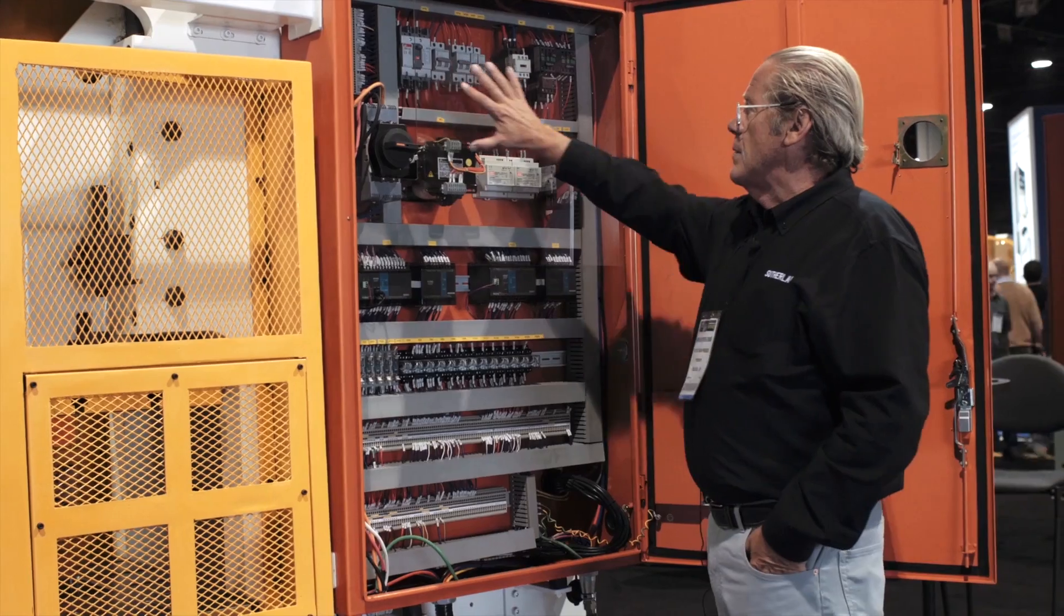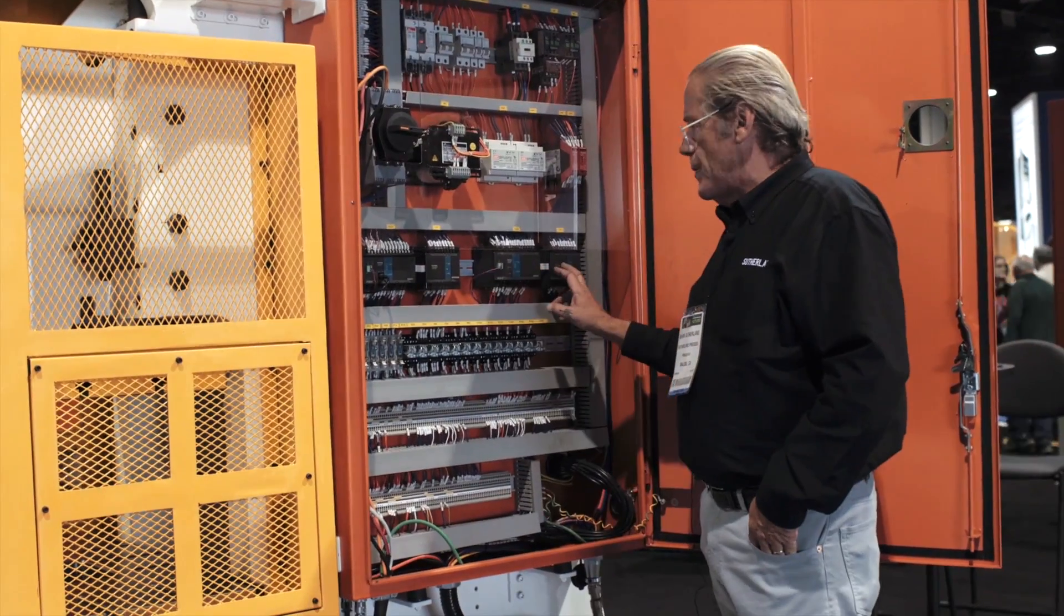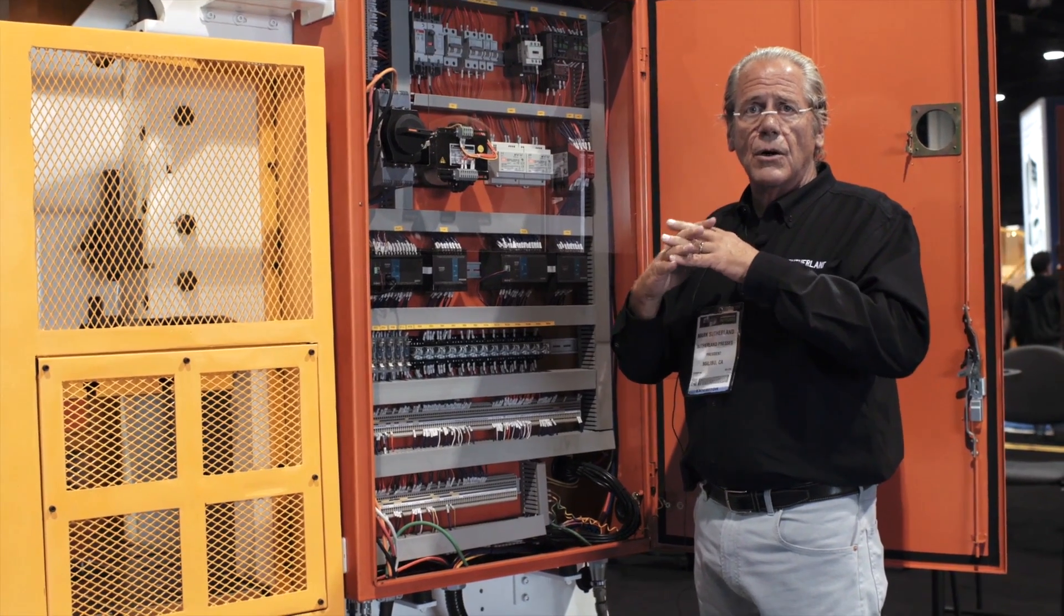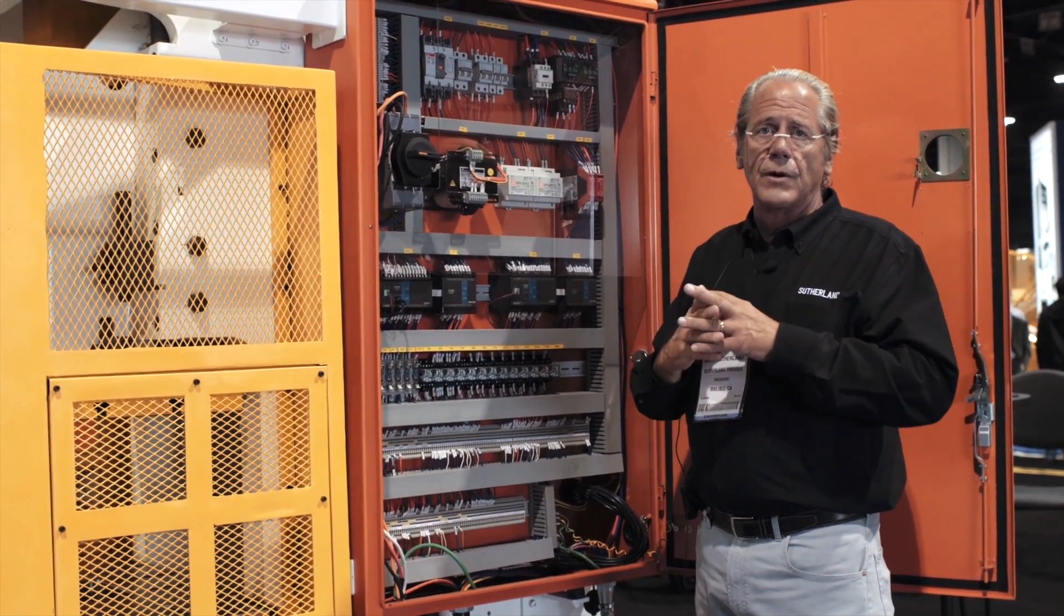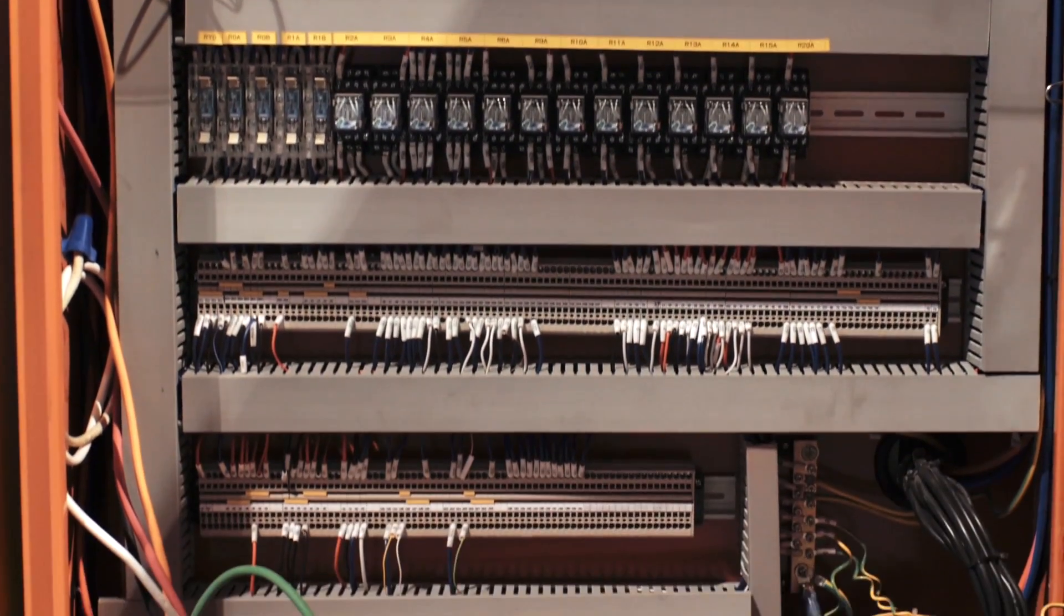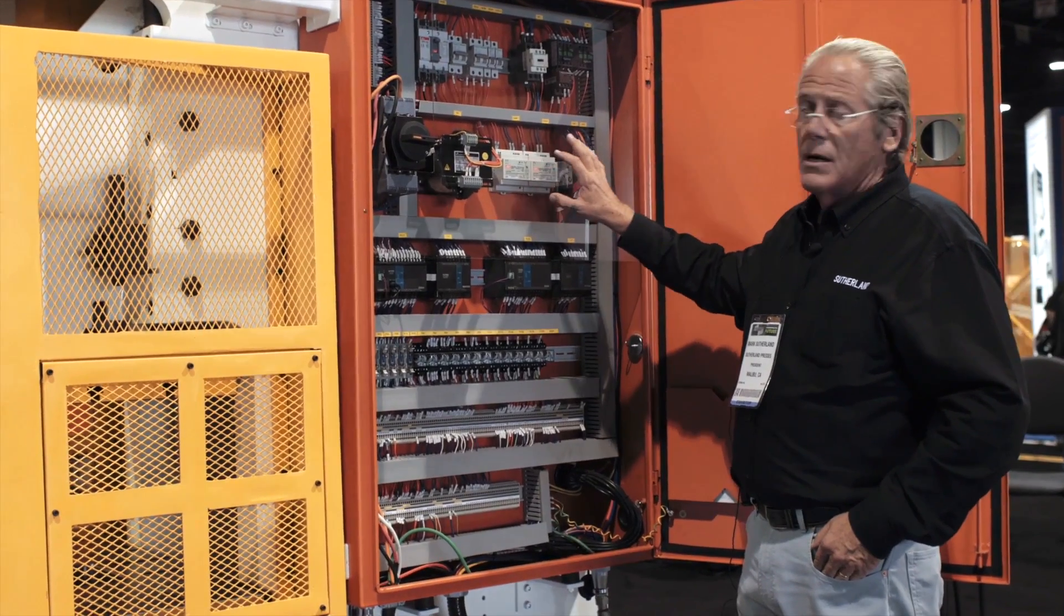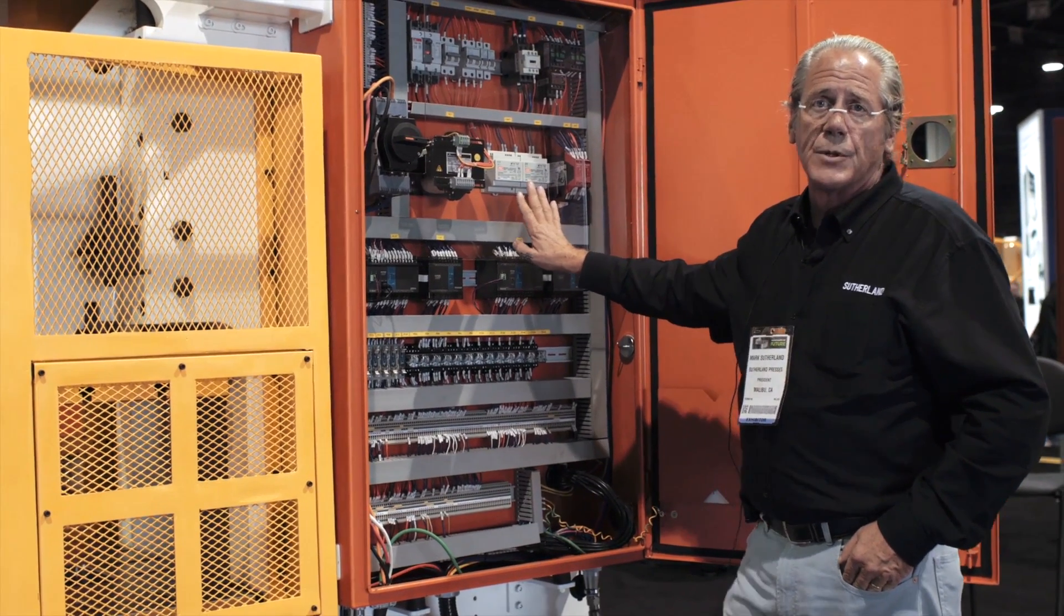High voltage on top, dual PLCs, programmable logic controllers with expansion modules. Those are cross-checking, so there's no possibility of clutch brake tripping inadvertently. Safety relays, logic relays, and then terminal strips. Very clean, done to our US standards, and meets CE requirements for Europe as well.